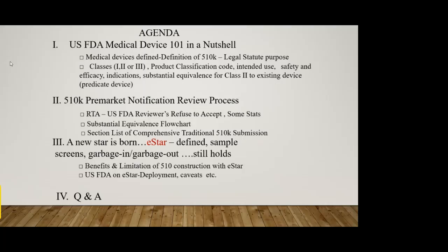that's when they switch over to what's known as substantive review, which is actually looking at your compilation submitted to make sure that you have chosen the right predicate device and that you have sufficient data to prove substantial equivalence, which is the whole essence of the predicate device, right?